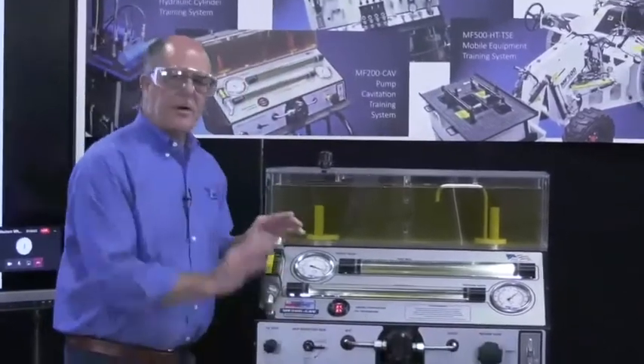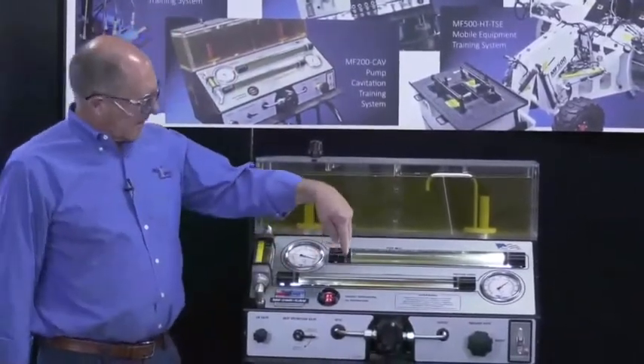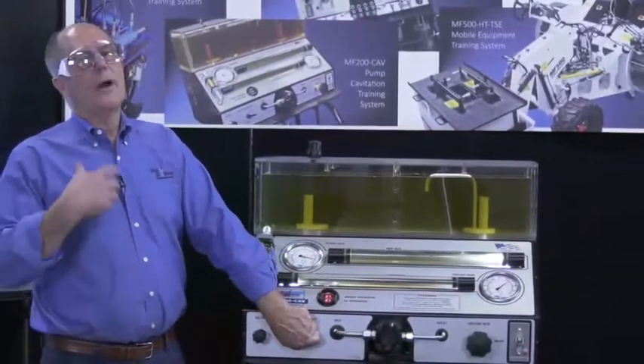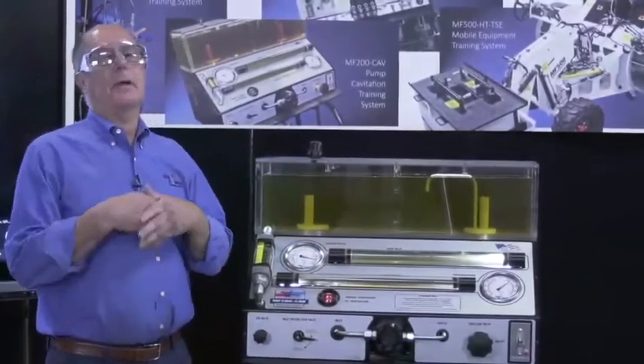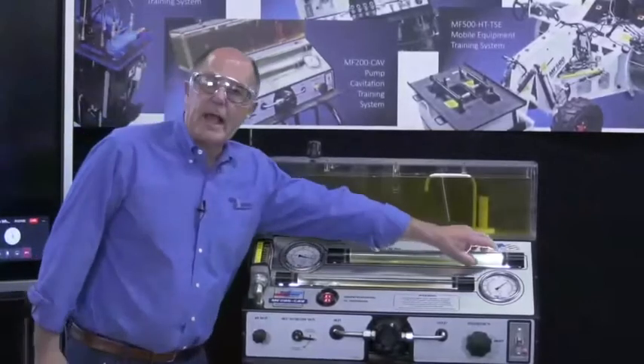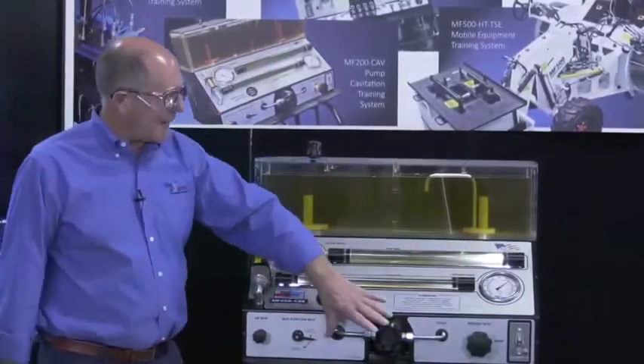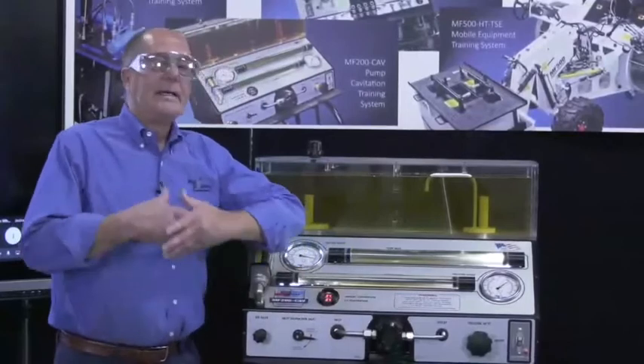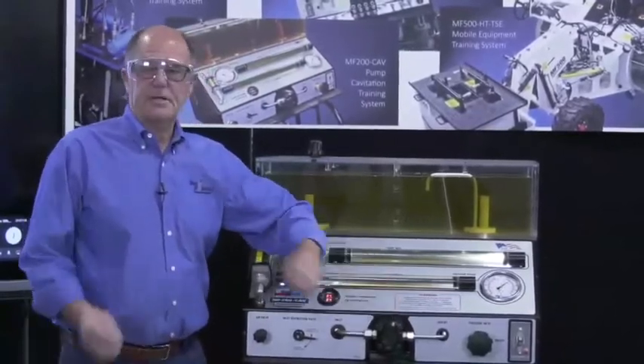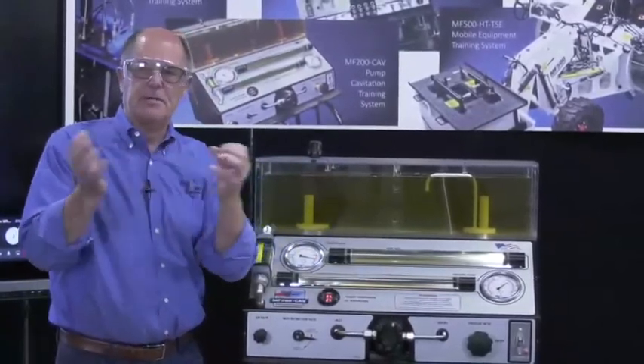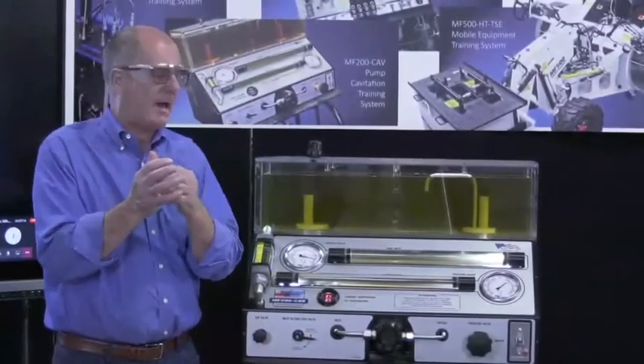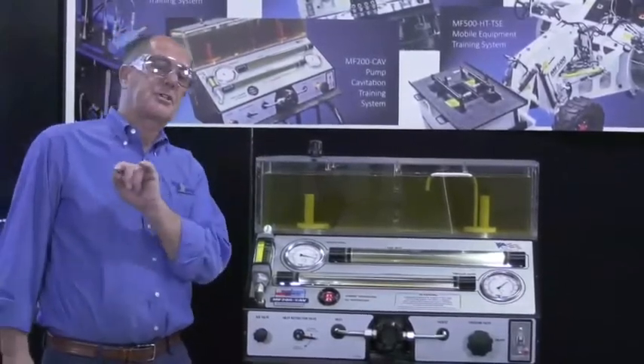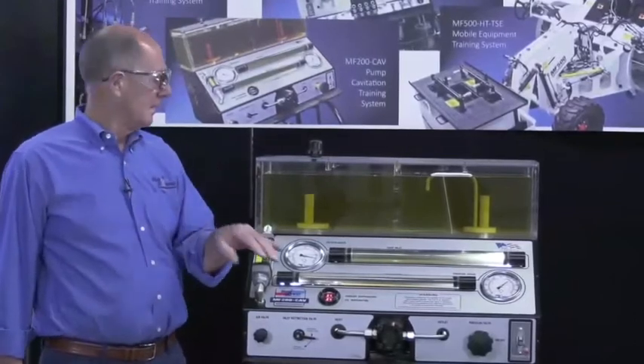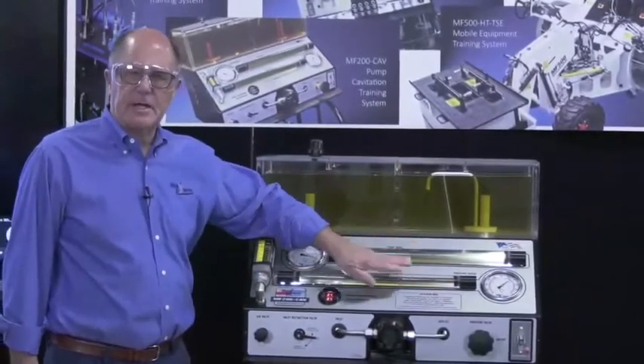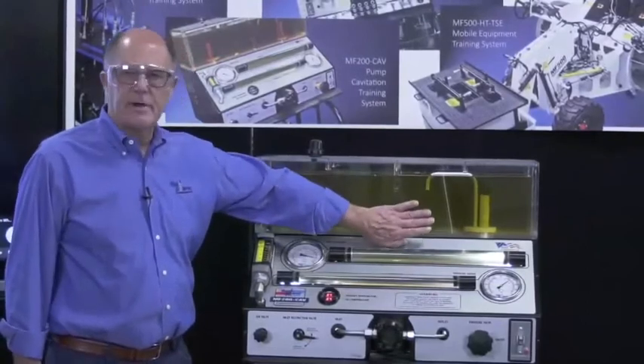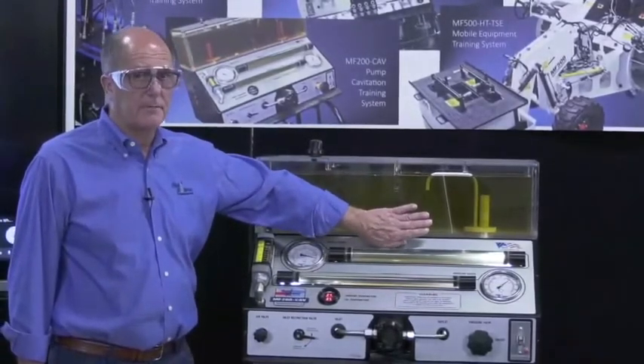All right. So here's a summary. I restricted the flow, replicating an overspeed condition of the pump, replicating its plug screen. The dissolved air came out of the oil, went through the pump, imploded, cavitation. High pressure is going to start to peel out the parts of the pump because as you're imploding in the pump, it's just beating it to death. All the pieces are going down line. It's a systemic failure. I saw no evidence of cavitation in my pressure line, and I saw no evidence of turbulence in my reservoir.